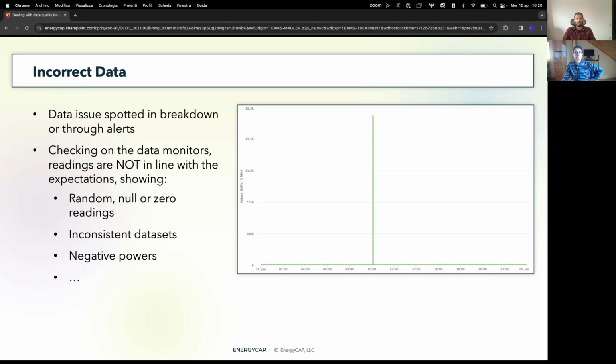active power readings, which can have energies calculated through the active powers, and we can set a filter in the active power readings so as to virtually flip the CT, basically. Basically applying an absolute value to those readings and turning negative power readings into positive ones, so that the calculation of energies through power readings is accurate.